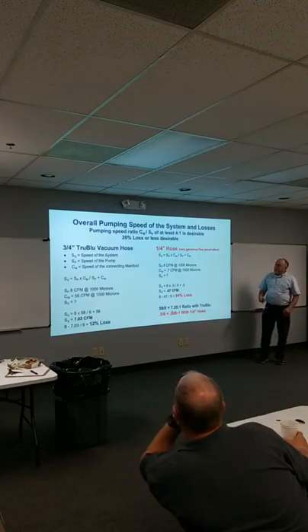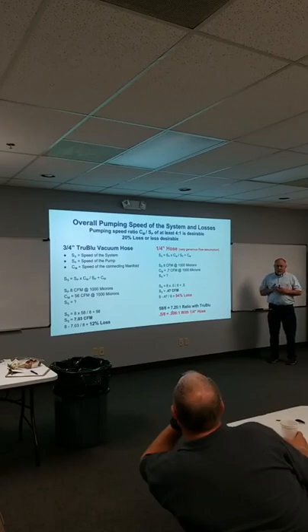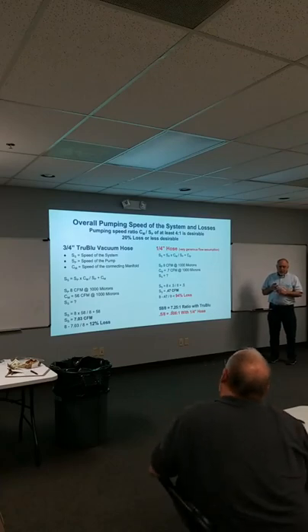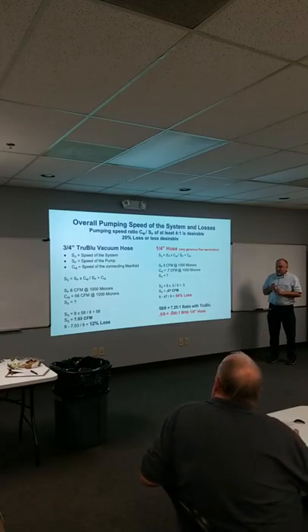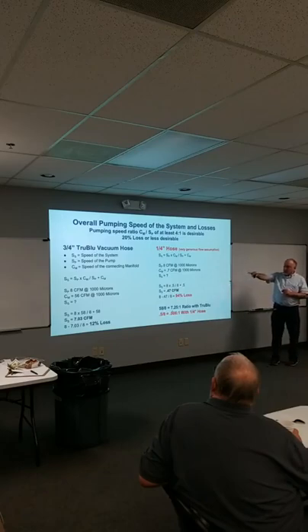All right? Now, what you gotta remember is there's 3 factors in evacuation. There's the speed of the pump, the speed of the hose, and then the speed of the system that we're dealing with. And a lot of people don't think about this all the time. And there's a formula that just says this, the speed of the system is the speed of the pump times the conductive speed of the connecting manifold divided by the speed of the pump plus the connecting speed of the manifold. It's just like an averaging formula there, okay?